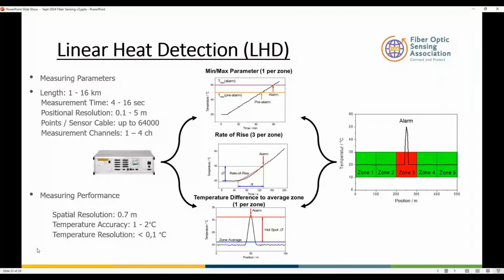So here's another application for distributed temperature sensing. Let me explain real quick what linear heat detection is. There's a conventional linear heat detection technology using a metallic cable, and essentially the cable melts and fails—that's how the alarm is triggered. This is not that. It's a bit of a paradigm shift, specifically in that nomenclature, linear heat detection.